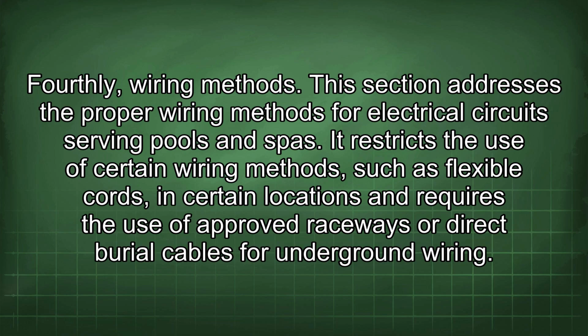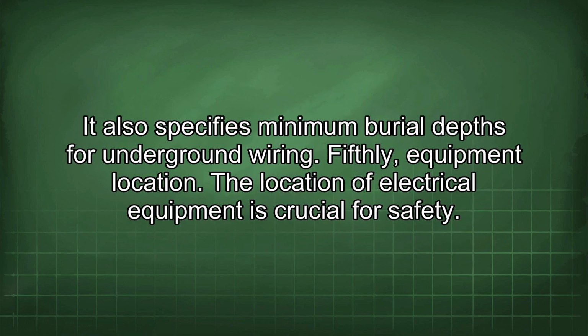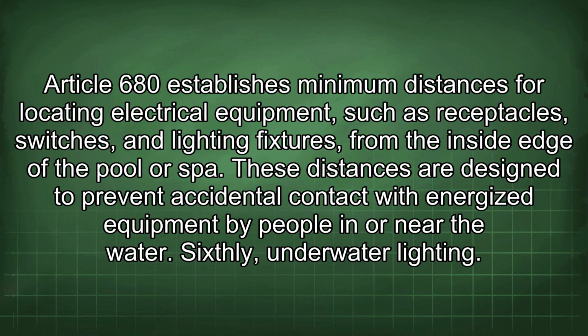Fourthly, wiring methods. This section addresses the proper wiring methods for electrical circuits serving pools and spas. It restricts the use of certain wiring methods, such as flexible cords, in certain locations and requires the use of approved raceways or direct burial cables for underground wiring. It also specifies minimum burial depths for underground wiring. Fifthly, equipment location. The location of electrical equipment is crucial for safety. Article 680 establishes minimum distances for locating electrical equipment, such as receptacles, switches, and lighting fixtures from the inside edge of the pool or spa. These distances are designed to prevent accidental contact with energized equipment by people in or near the water.